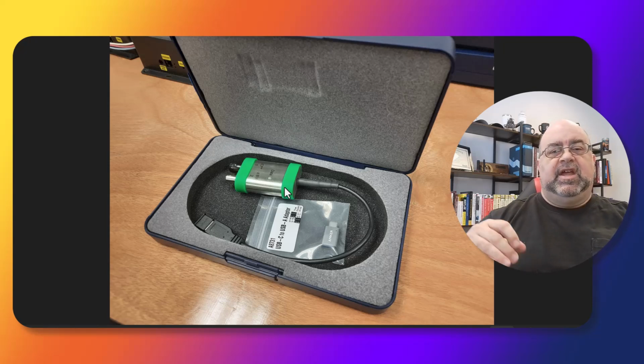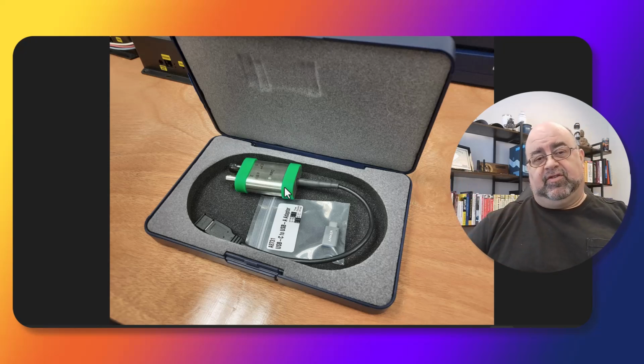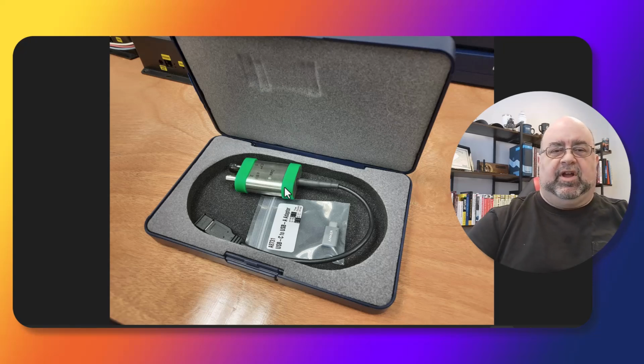That's in the low end of the supra harmonics, which can go from 2 kilohertz to 150 kilohertz. We go out to 22 kilohertz. For most industrial systems, that's good. If I'm doing grid type work, that's not quite good enough.